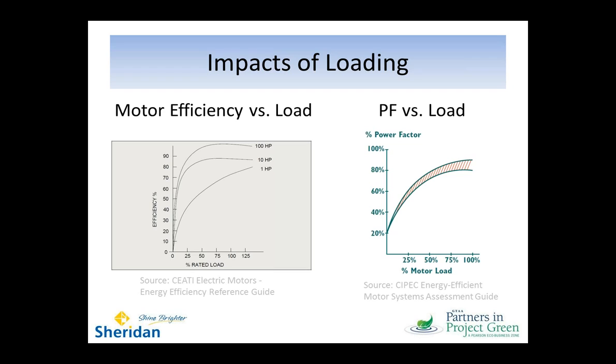And so it's very important to avoid those situations where you have a machine idling without drawing an adequate load on it. And you can see that also in the power factor curve on the right, that very quickly our power factor drops as we lighten the motor load. And so we can suddenly have a very distinct and drastic effect on the plant power factor by allowing these motors to run lightly.